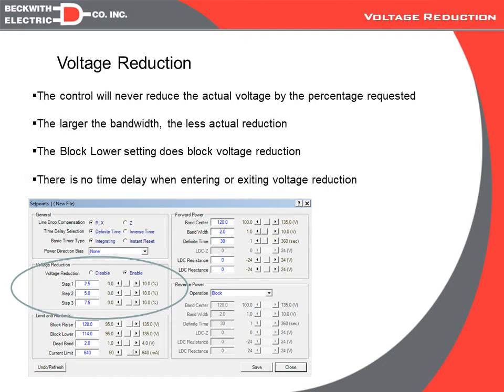So again, we have three different settings on voltage reduction. They're under the set points window, and you can see first of all we have to enable it if we want to use reduction, and then we can assign different percentages for each of the three steps, and those percentages can go from 0 to 10 in 0.1% increments. So those would be the valid settings for the reduction, and again we also need to coordinate that with the block lower setting to verify that we're going to get the full reduction desired.